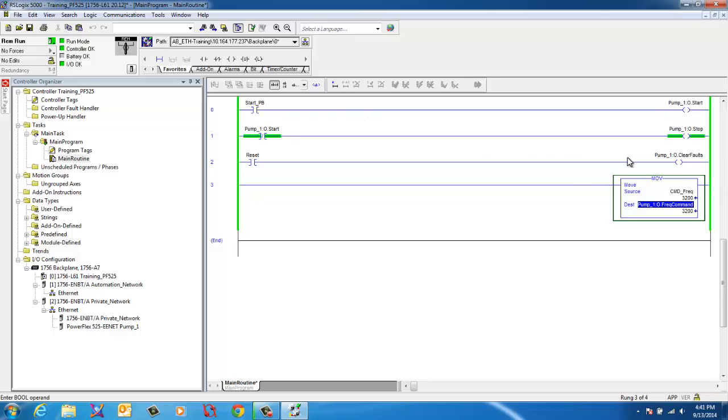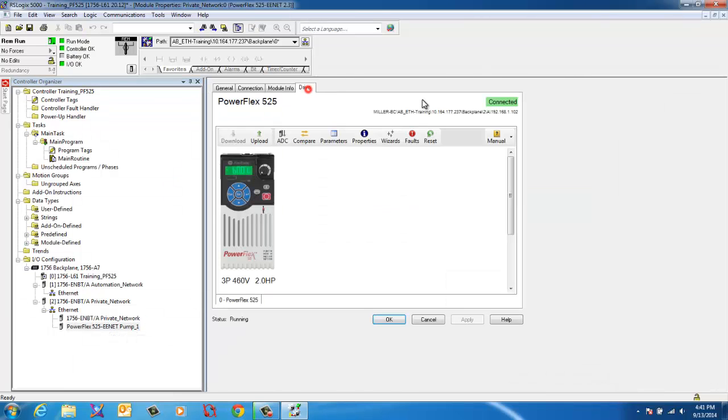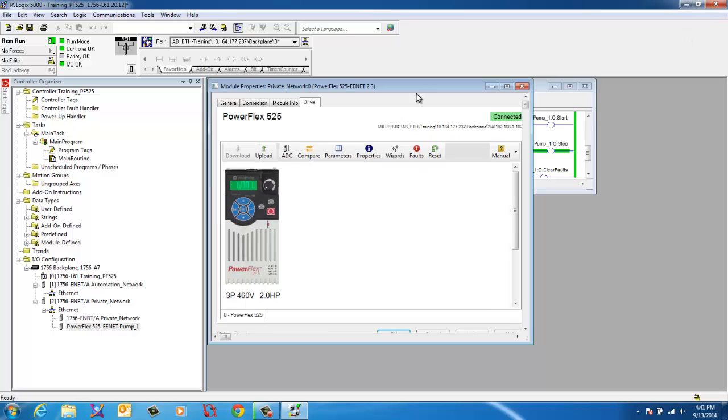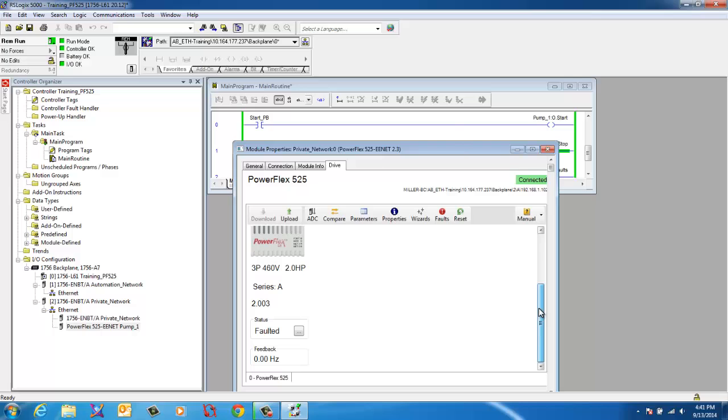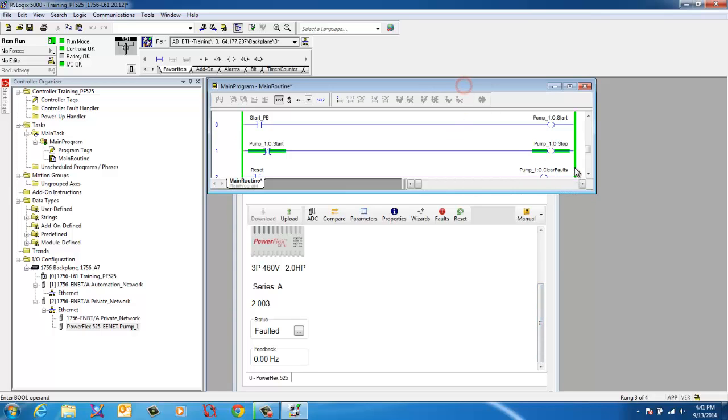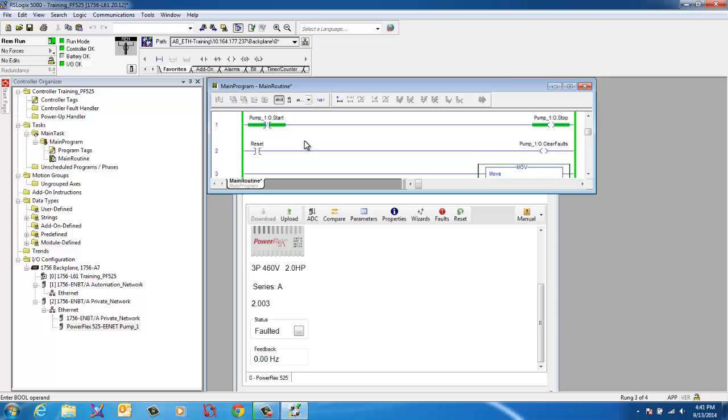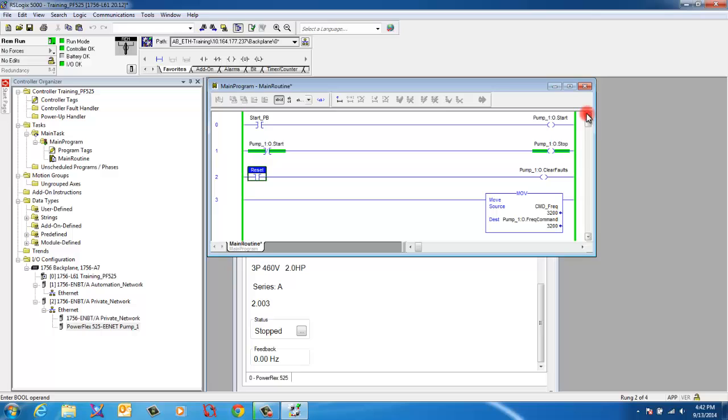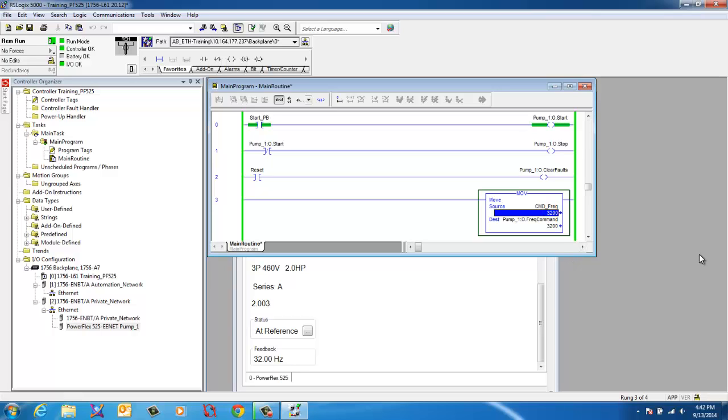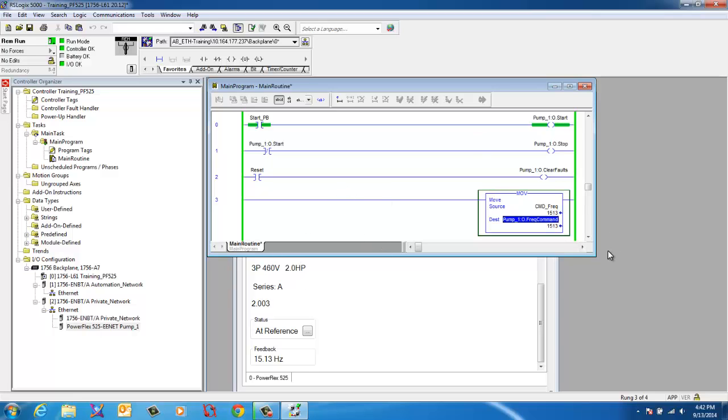Now when we go to start this drive remember we're still faulted so let's pull up this. Go to the drive, minimize this window, drag it down here just a little way so you can watch it. Clear it's faulted right now. We're online, we're connected with the drive, there's no errors. I'm going to toggle the reset. You'll watch it be able to reset. So the drive is no longer in fault. It's clear, ready to start. Scroll this down just a little further. Look up the top, go at 32 Hertz and we're going to go ahead and start the pump. The pump drives running. Within two seconds it got up to 32 Hertz. Like I said you can change this on the fly. We're going to do 15, oops not point, we're going to do 15.13 Hertz. Type in 1513, drops it to 15.13 Hertz.